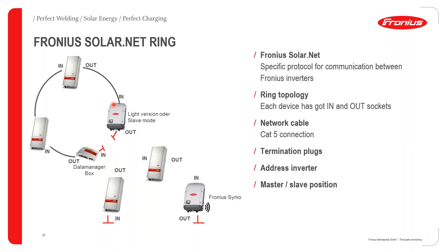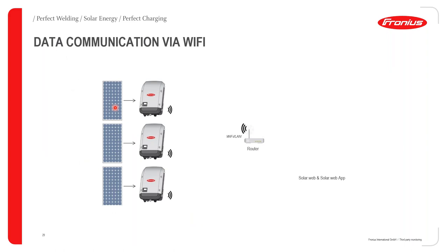Even if you have an inverter with a Data Manager integrated, you would need to disable that Data Manager because there can only be one master in one SolarNet ring.